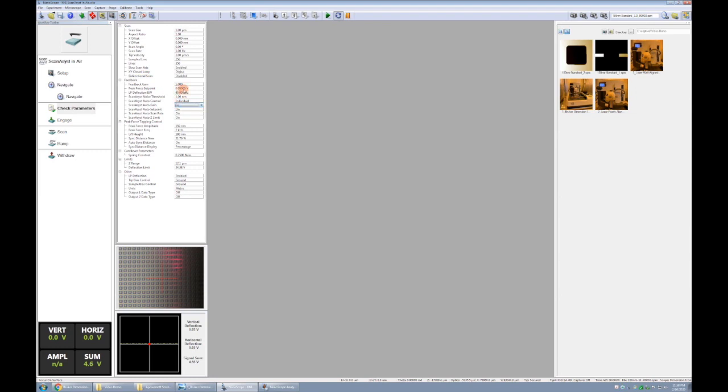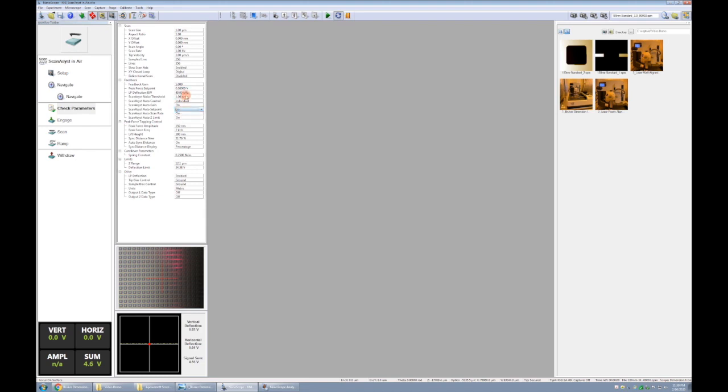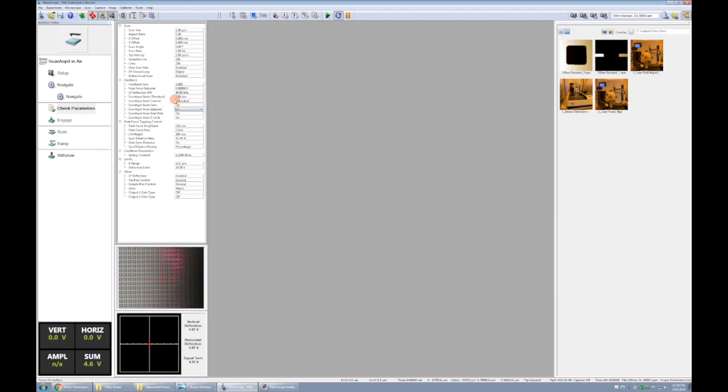The feedback gain is a value that we'll ask the software to automate during our scans, and I'll show you that when we're scanning in the next video. Peak force set point is the amount of force that we're trying to achieve with each tap when using peak force tapping mode. This is something that we can allow the software to automate. Usually I'll leave this on at the beginning, and then once it lands, we'll let it find a happy peak force set point. Once it's there, we'll typically lock it to off so that we keep the same force throughout the rest of the scan.